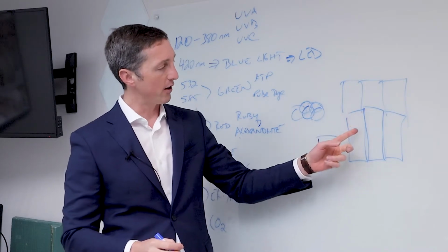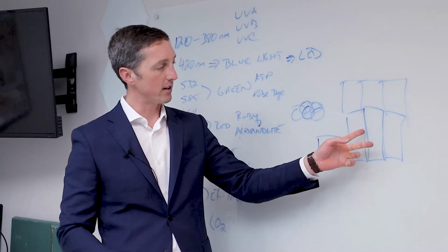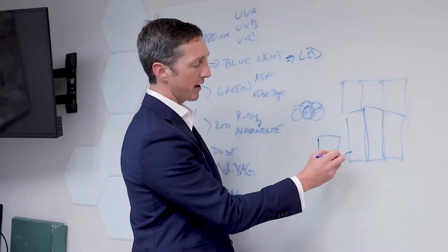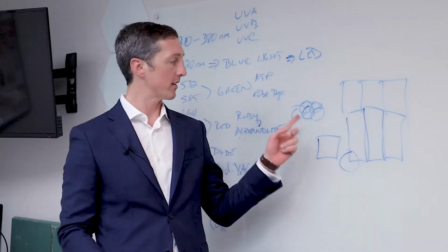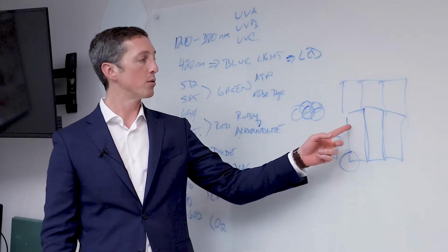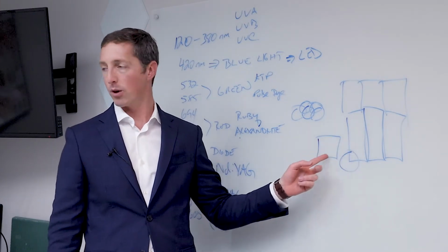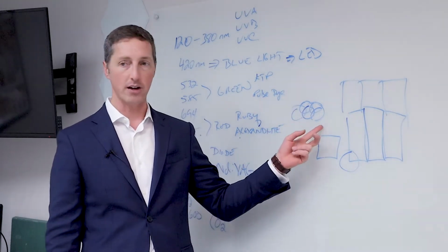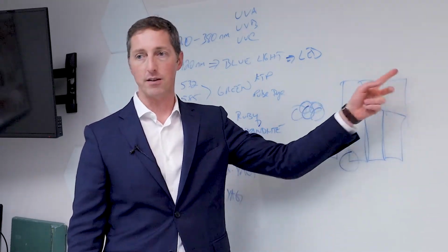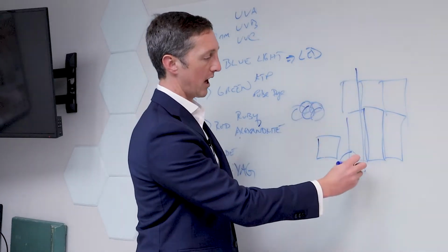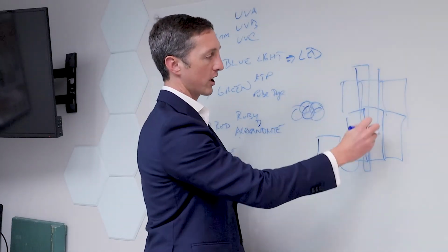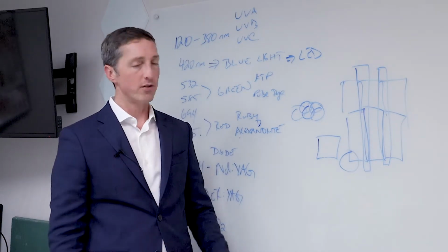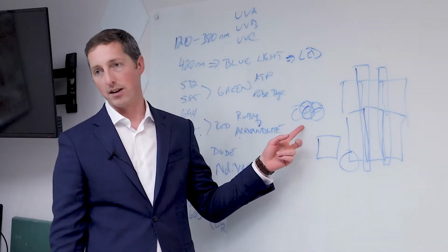You can tell here though that if you're not overlapping generously, you're not going to account for the scatter effect. And you have more scatter, particularly with a square or rectangle, especially around the corners, than you do with a circle. So you really want to avoid this type of beam profile when doing laser hair removal treatments. This is what you really want to get a very effective treatment. This would not be very effective. You could have striping, so you could have non-responsive hair going right down the center here and looking like little tiger stripes to some degree, whereas here you won't have that at all.